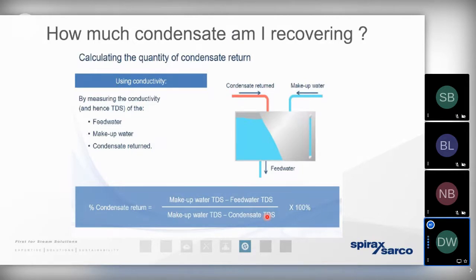So it's in a fantastic condition for keeping the hot well or the feed tank at a nice high temperature. Hot water in the feed tank means that we get less stress and thermal shock placed on the boiler. It means we're producing steam more rapidly and more responsively. It means we're producing steam more efficiently from an energy perspective. And condensate has already been chemically conditioned, so it's in a perfect state for going back into the boiler again.